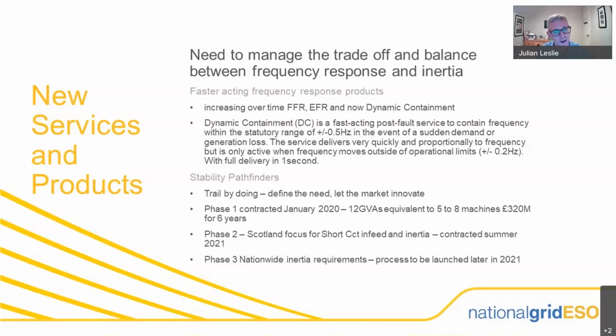Or do you go very, very high on inertia and then less and slower frequency management products? So we've tried to define the key trade-off point for us here in GB. Last October, about 15 months ago, we introduced something called dynamic containment. This is a very fast frequency response product that's monitoring the frequency all of the time. When we have a fault in the system and the frequency falls rapidly, this service delivers very quickly, and it can deliver the full capability. So if it's a 50 megawatt battery, it can deliver a full 50 megawatts within that first second.